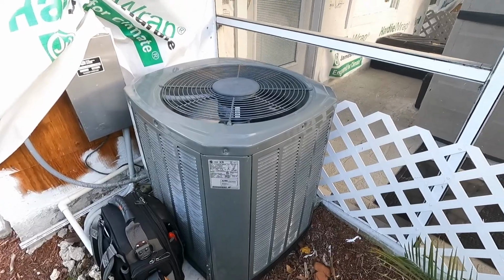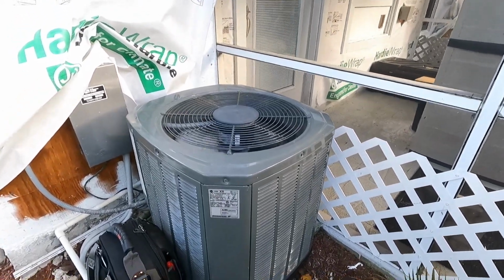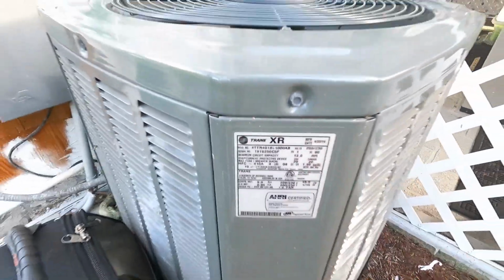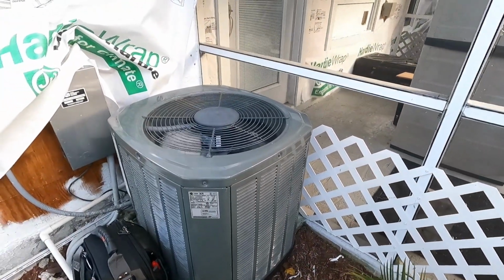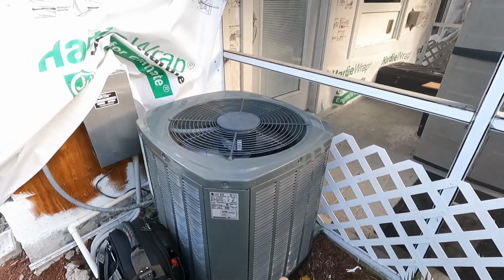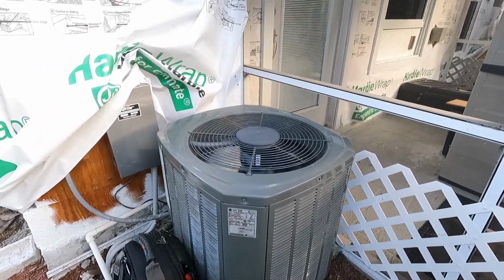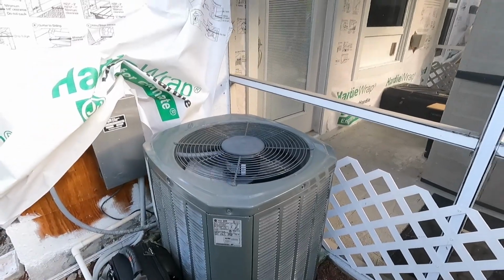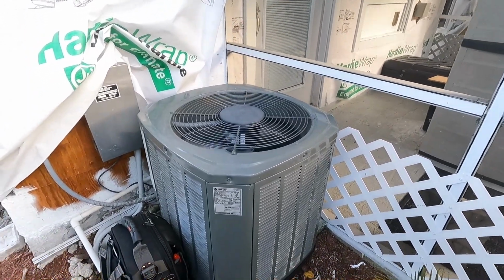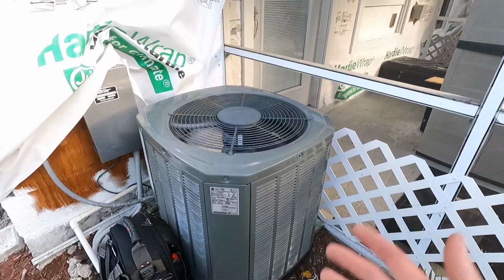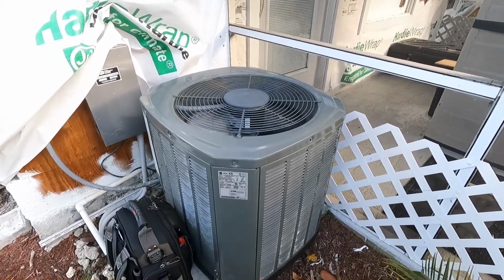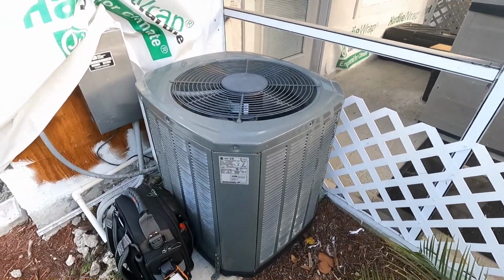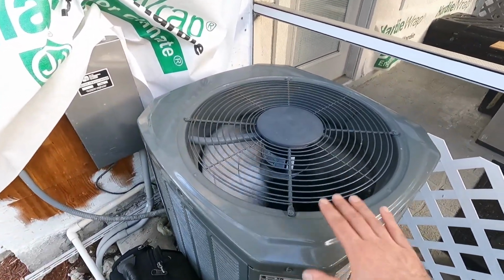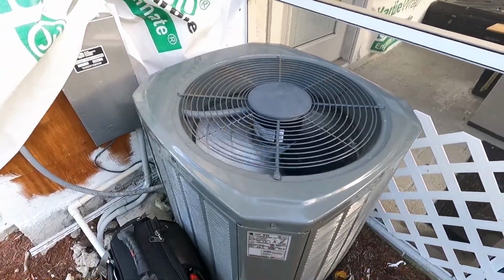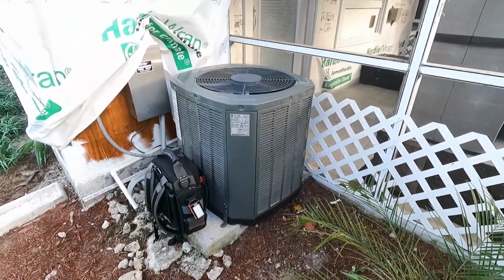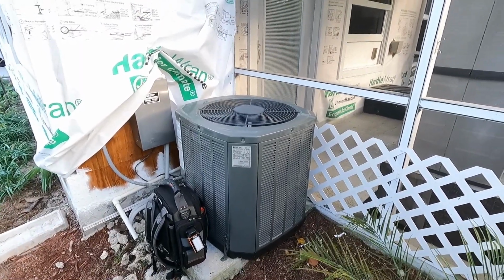So, sometimes you're going to have noisy condensers outside, especially the older they get, things work loose, things vibrate loose. Part of your maintenance, you're pulling things apart to clean it anyways, so it's a good idea to, with your impact, lightly hit some of the screws, tighten things down, get it back to just a solid unit as far as all the construction goes. And most times that's going to take care of your little bit of noise you deal with in the outdoor unit. So overall, I think we're all good to go here. Just recommend their maintenance gets done here shortly.